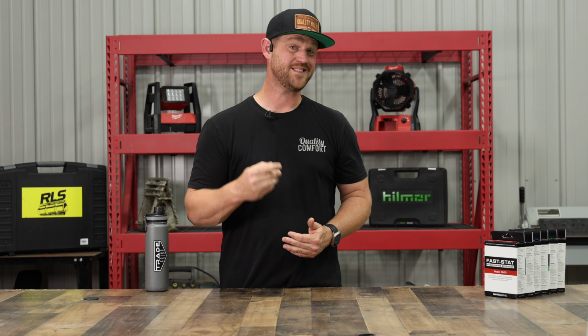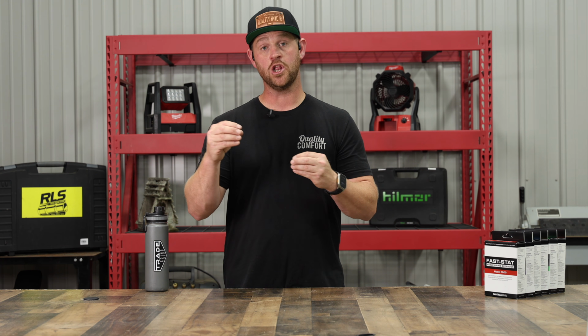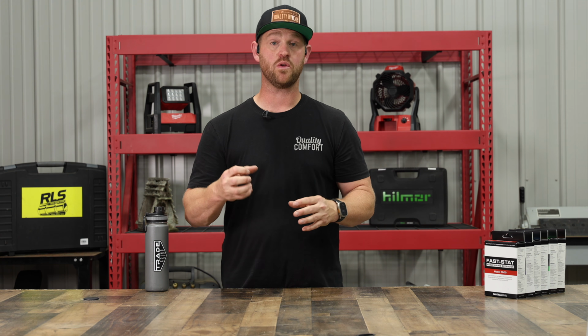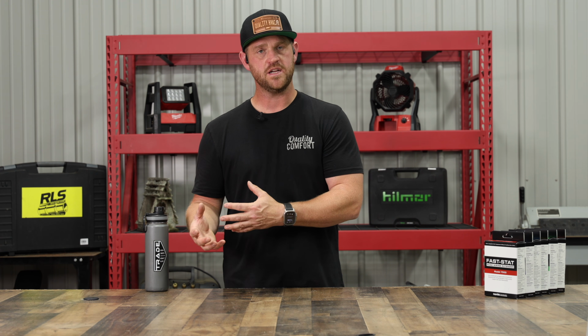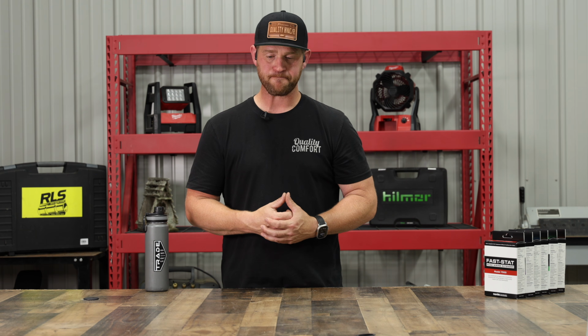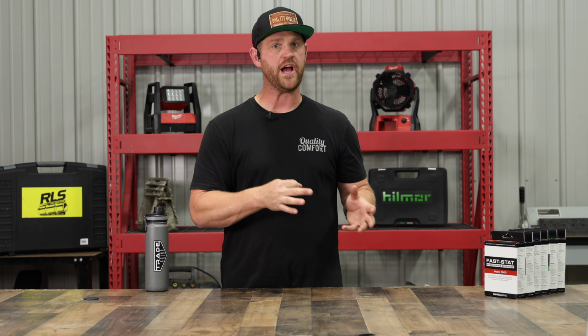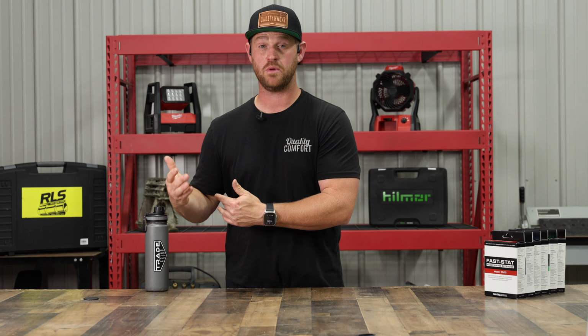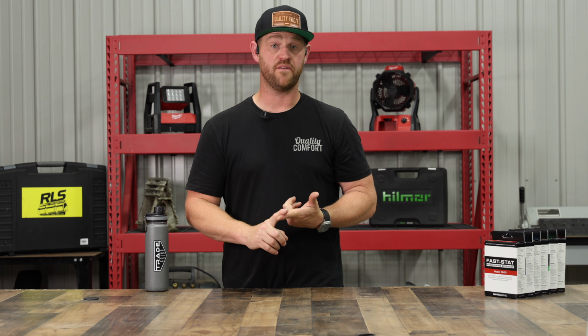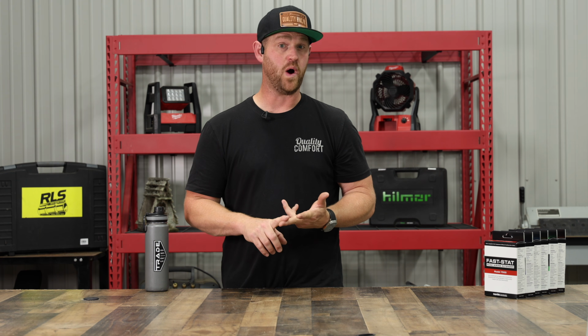That's one reason. Second reason is because we're able to run at lower speeds, we do get more runtime, but we can also run at lower blower speeds. That indoor fan, if we can slow that down a little bit, we can wring out more moisture out of the air as well. So there's multiple components, multiple things going on here that allows it to be better at removing that humidity. So again, the three main reasons that we're talking about why you would even want to go to something that costs you more money up front is it's going to feel more comfortable in the house. It's going to be quieter, right?